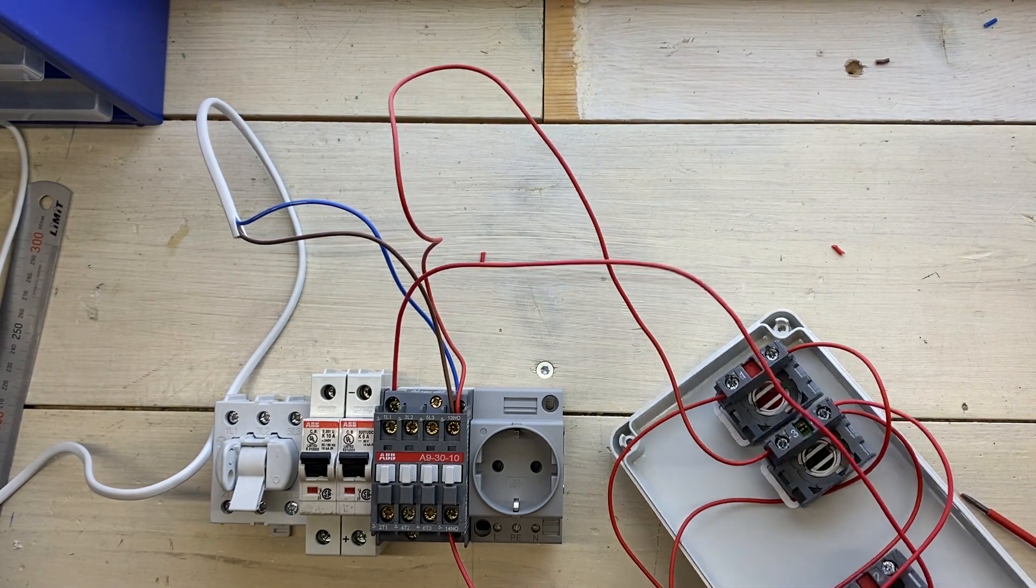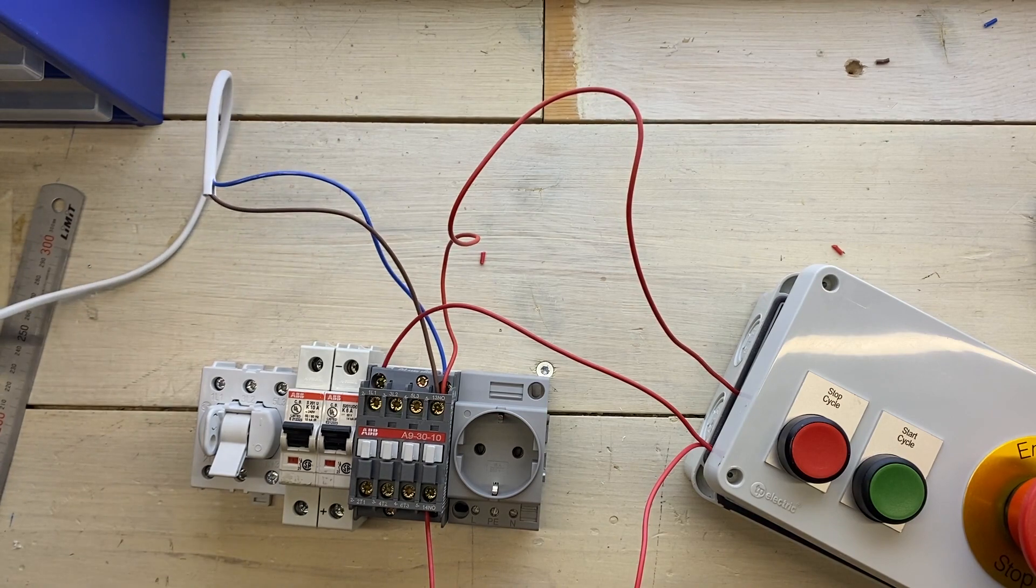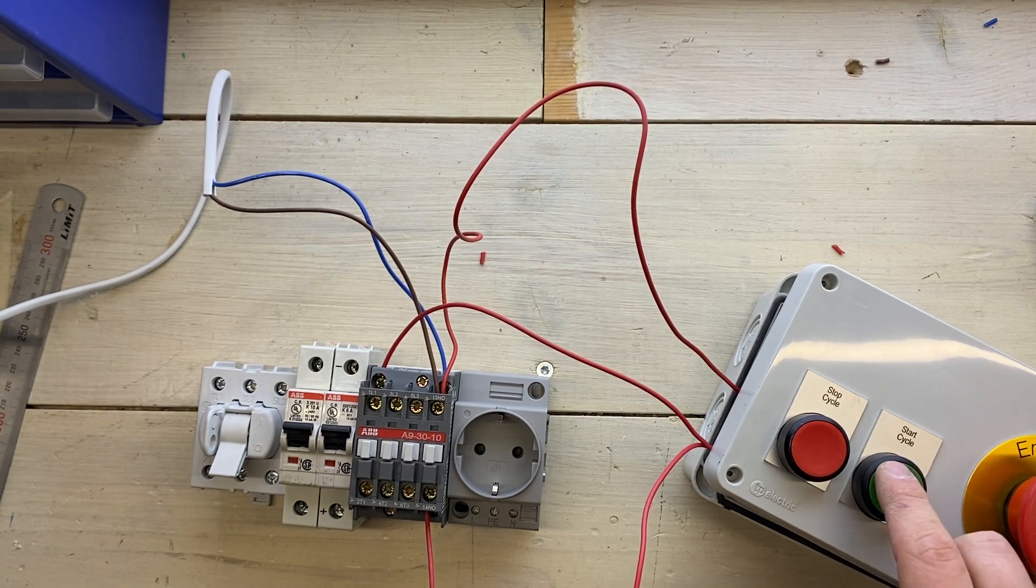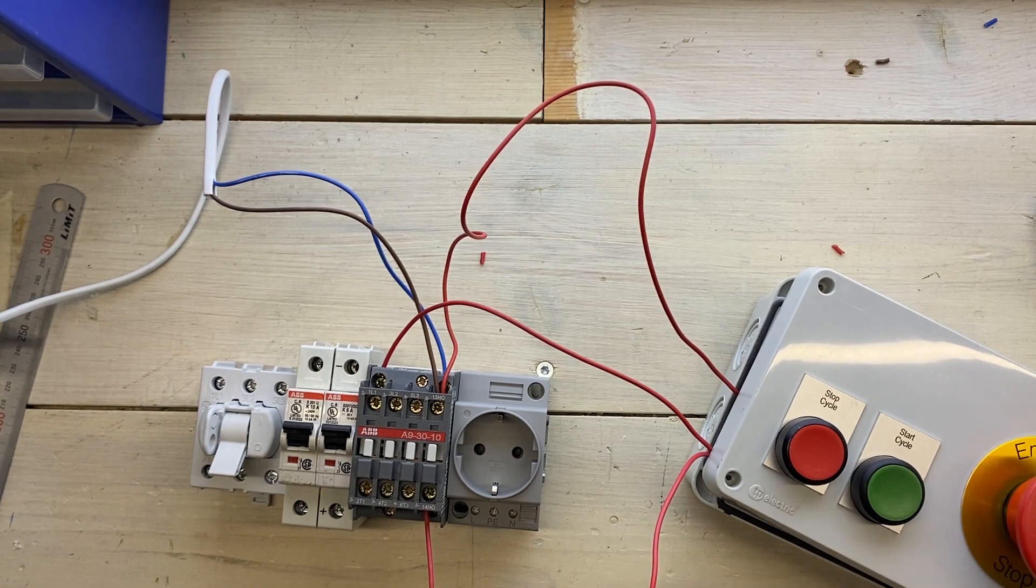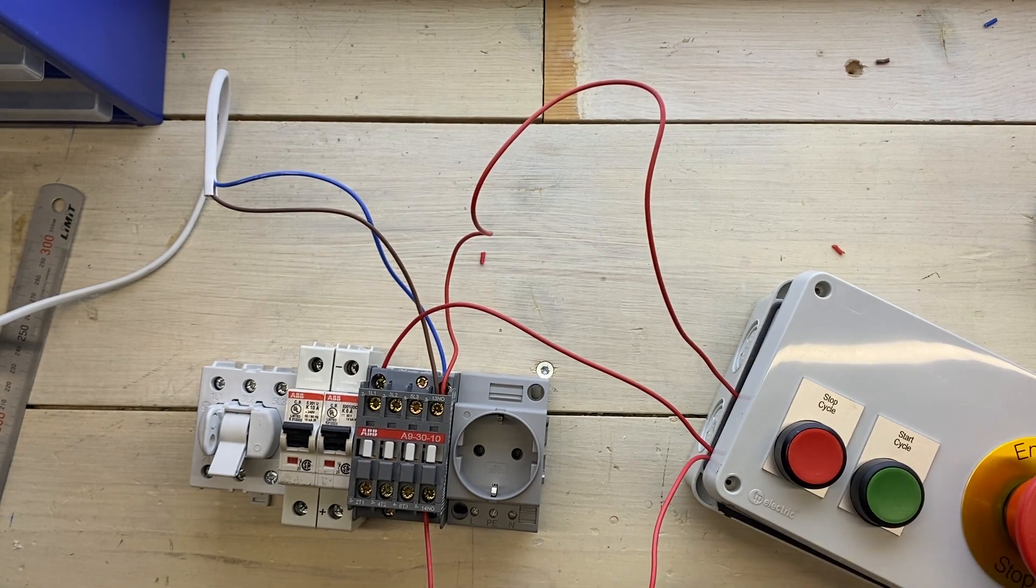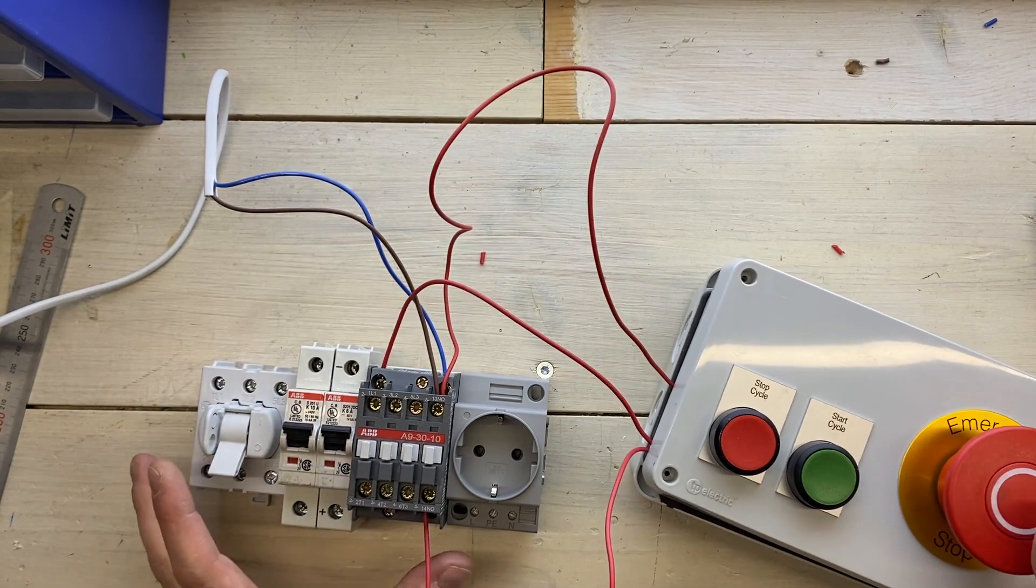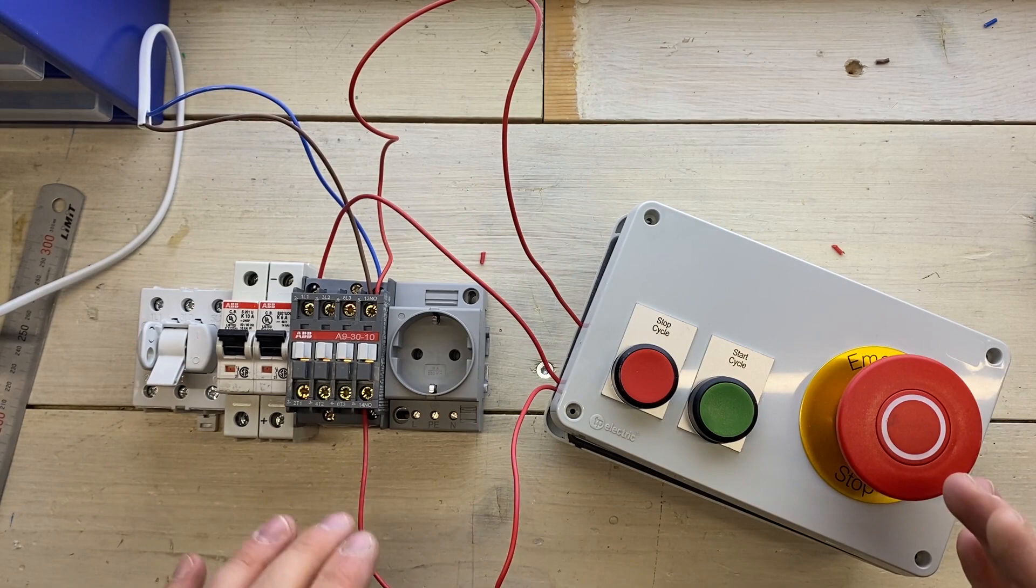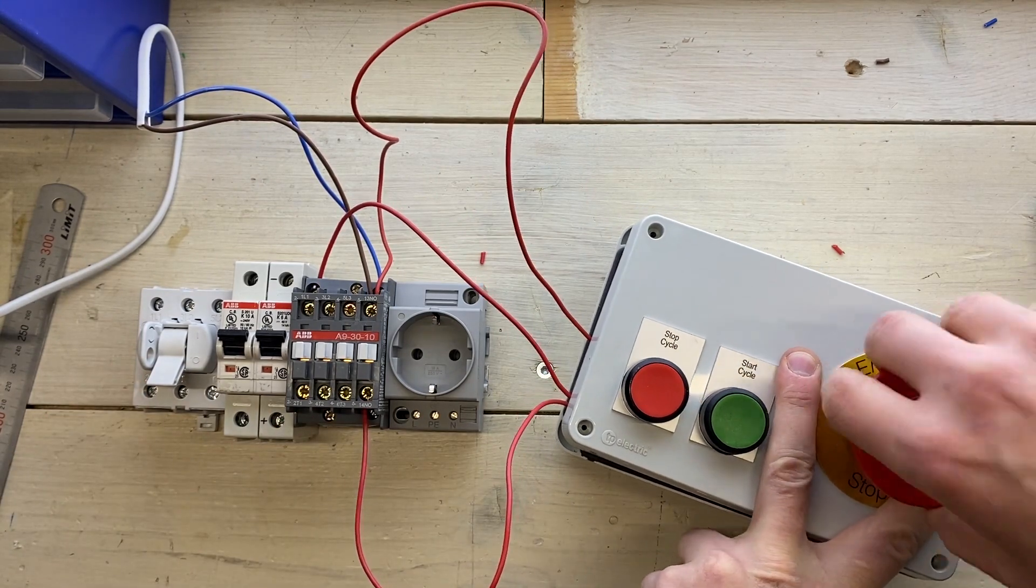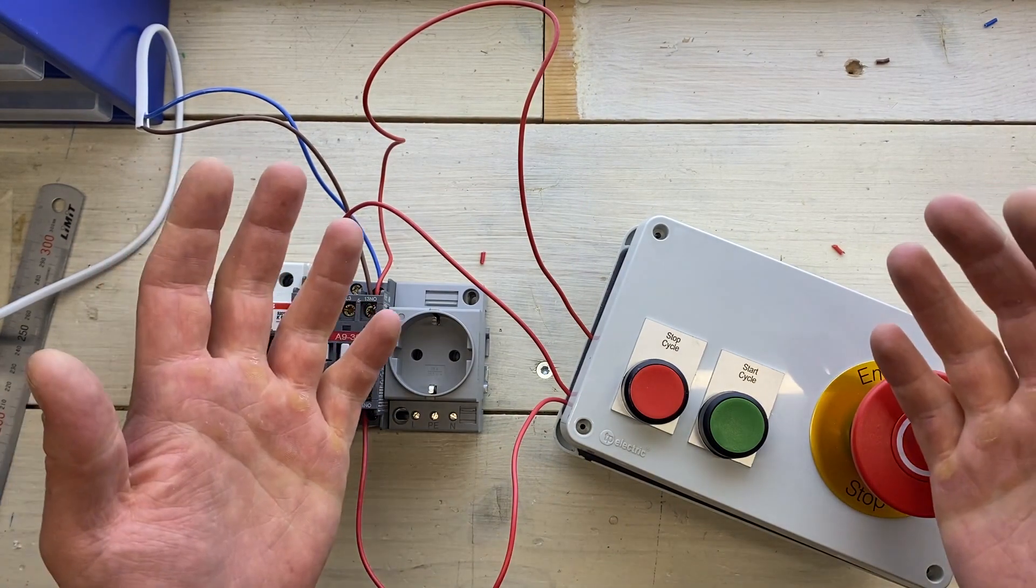So let's turn it on and see what happens. Hopefully nothing blows up. And if I push the start button, the contactor should pull. And if I push the stop button, it should release. And the same thing. If I push the start button, it pulls. And if I push the e-stop, it releases. And now the important thing is that to reset this circuit and actually get the contactor to pull again, I have to both reset the e-stop and push the start button. And that is how a safety circuit should work. Ta-da!